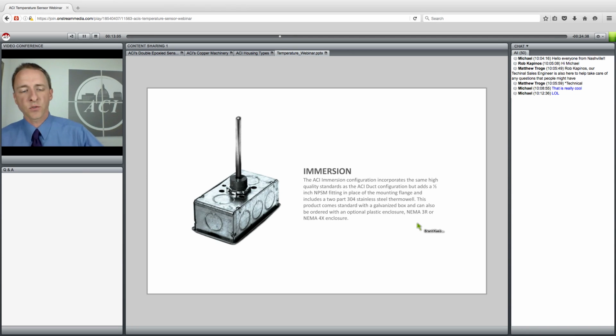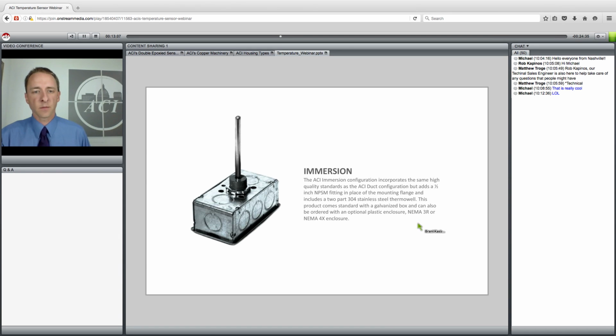Next are our immersion sensors, and they fit into a standard Thermowell that is 1/2 inch NPT. So this is a 1/2 inch thread here, and the external thread of our wells is 1/2 inch as well. One application or ordering note when it comes to our immersion wells is we measure our immersion sensors and our immersion wells from below the thread of the well. So from here on to the tip of the probe. For example, this is a 4-inch well, and that's measured 4 inches from here to here. Now the probe itself, when it's screwed into this well, it's actually a 6-inch probe because the probe goes all the way to the end of the thread.